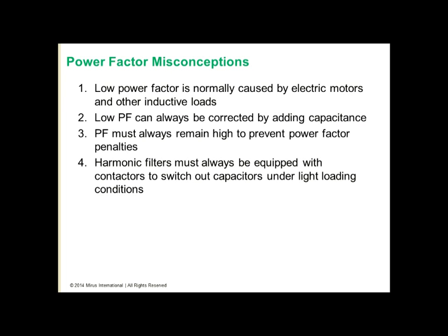The fourth is that harmonic filters must always be equipped with contactors to switch out capacitors under light loading conditions. In reality, many harmonic filters do require switching out contactors under light loading conditions, but not all. So a properly designed harmonic filter will not require switching out of capacitors.